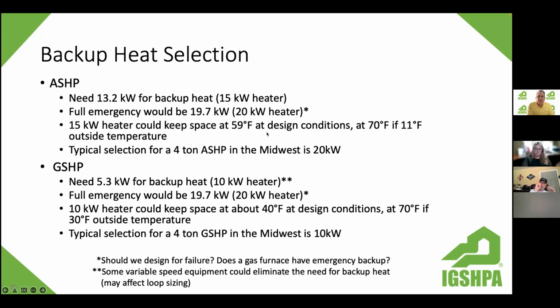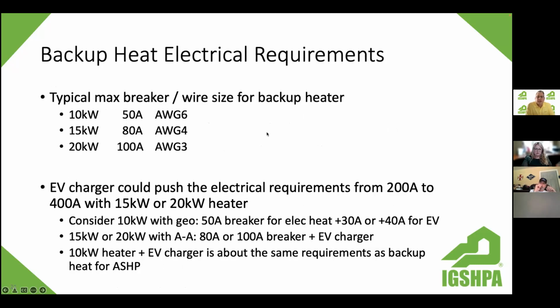That has some pretty big impact on our electrical requirements, and in some cases we might be pushing it a little bit. It depends on what other appliances are in that house. In most cases, our 10 kW heater is going to take a 50 amp breaker and number 6 wire. Okay, so that would be our geothermal unit. If we go with the 20 kW on the air source heat pump, take a look at this breaker requirement: 100 amps and number 3 wire. So we're adding quite a bit of cost.